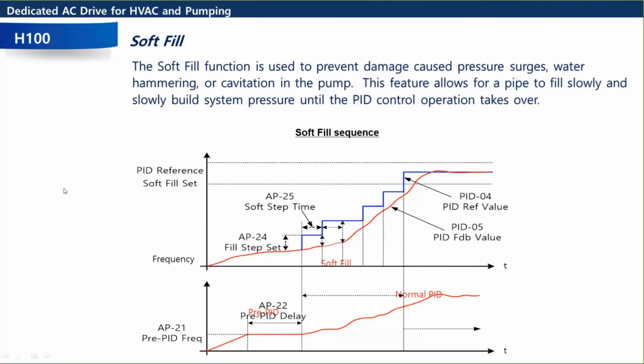All right, so we have a soft fill. We're talking about pump stuff, so I think most of the slides are going to switch over to pumping things now. Soft fill is commonly used in irrigation. You may hear it called pre-PID or a pipe fill. Let's say you have a large irrigation system and you power it up in the morning and start building up pressure with all the pipes totally empty. That could cause some pressure surges, some water hammering, and some cavitation in the pump, because everything's dry.